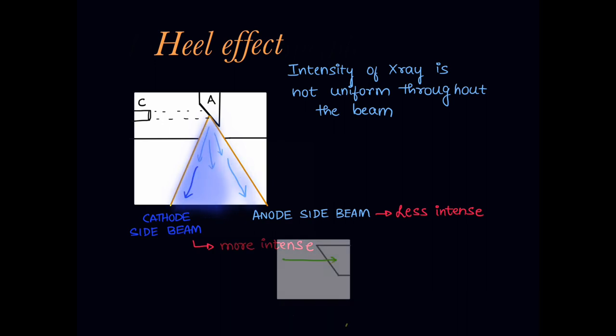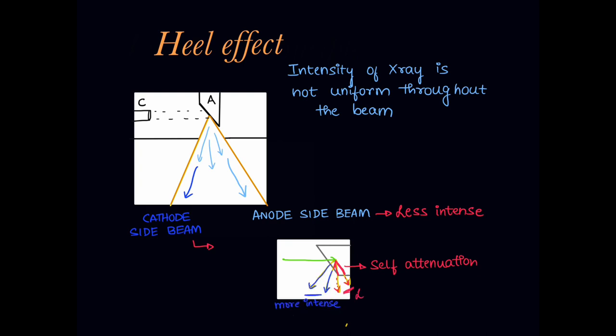The second principle is called the heel effect. It means the intensity of the primary x-ray beam produced is not uniform throughout the beam — the intensity varies. Here is the cathode and anode, and once the primary beam is produced, there are two sides for the beam. The anode side of the beam is less intense, and the cathode side of the beam will have more intense x-rays. More intense towards the cathode side and less intense towards the anode side. The reason for this is self-attenuation of the primary x-ray beam by the anode itself.